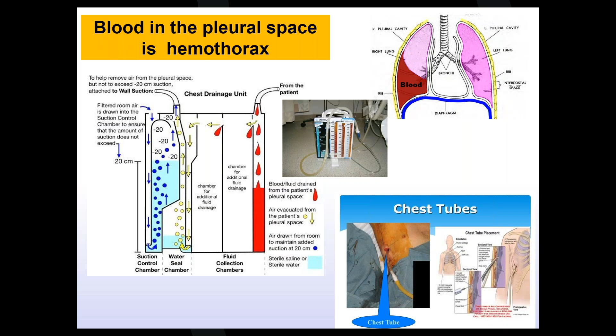So then it's graduated so that nurses can keep track of how much fluid is being removed. So if you see bubbling the next time you're in the unit and you see a chest drainage, and you see little bubbles going on, that's a good thing, because it's venting excess vacuum back out to the atmosphere. It's going through the water and it's bubbling back out. So that's how you know it's working. In other words, if there's no bubbles there, you've got an issue.